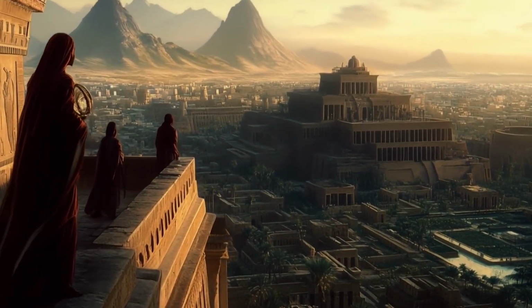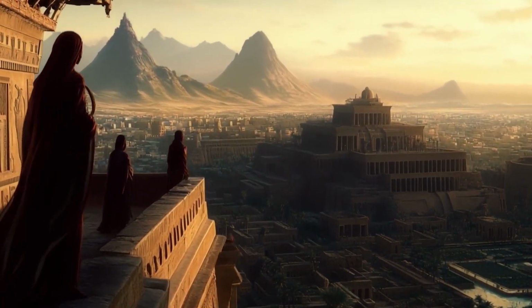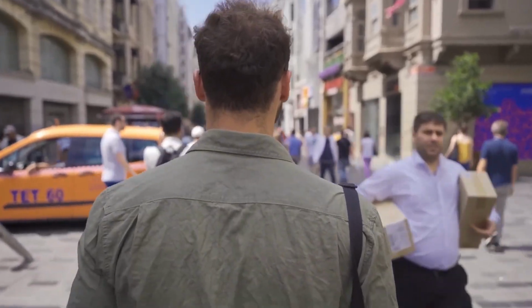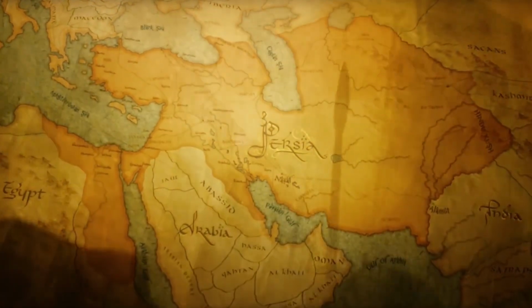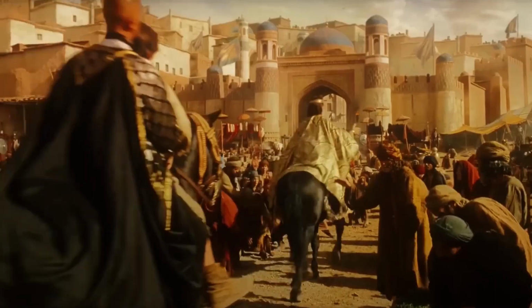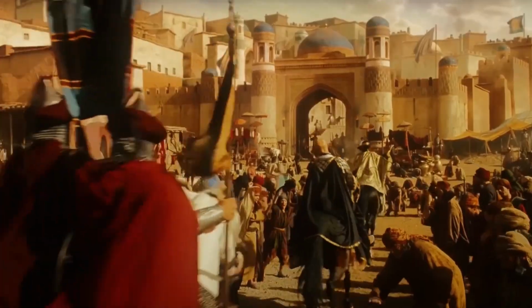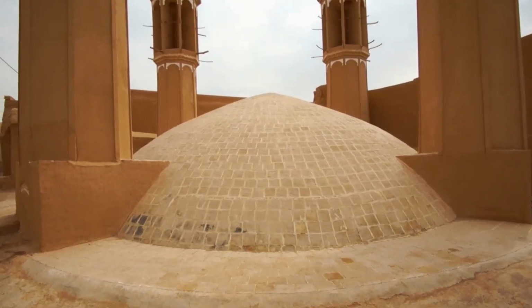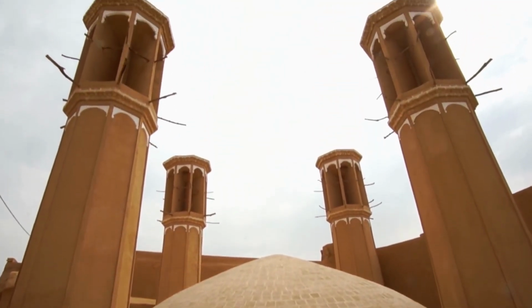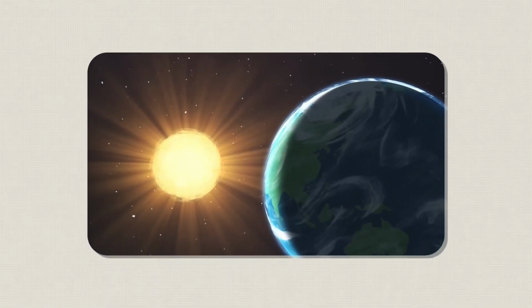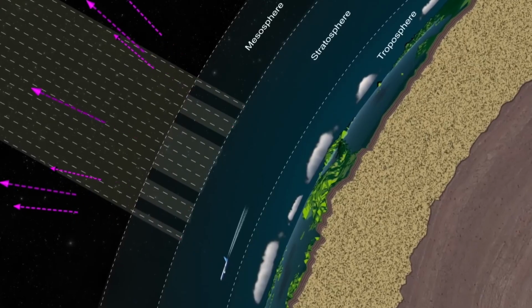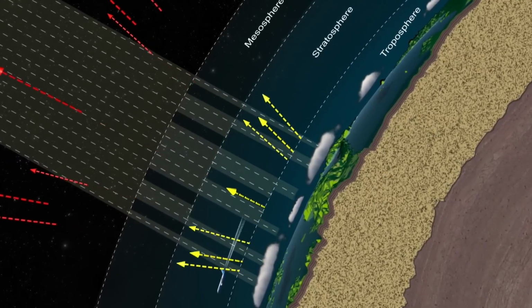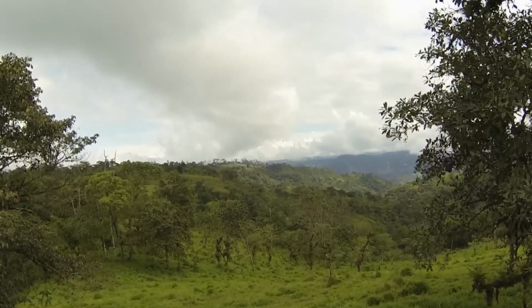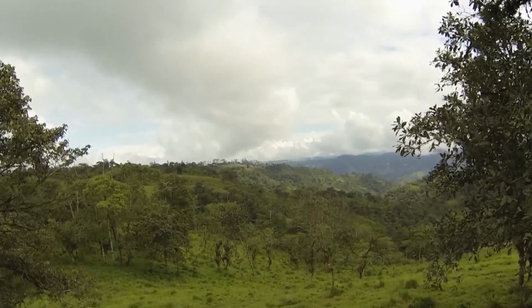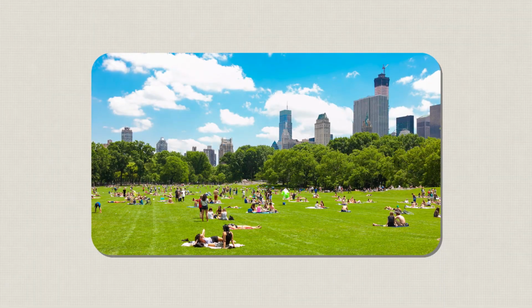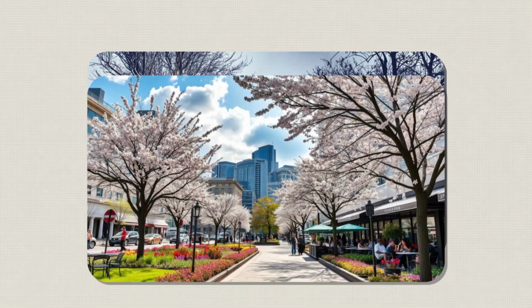To understand why this technology was buried, literally and figuratively, you have to go back to where it started. The oldest confirmed use of earth-cooled air systems dates to ancient Persia, in the same desert cities that gave us the badgir wind catcher. Persian architects understood something that took modern building science centuries to rediscover. The Earth itself is a thermal battery. It absorbs heat slowly, releases it slowly, and at subsurface depth reaches an equilibrium temperature that mirrors the annual average air temperature of that region: not the summer peak, not the winter low, the average.